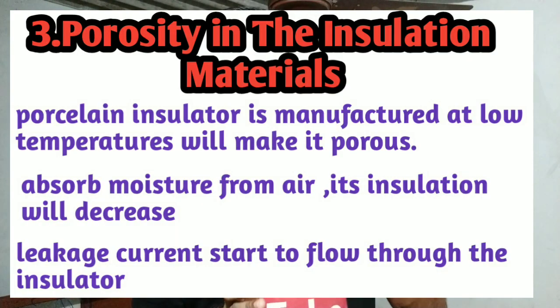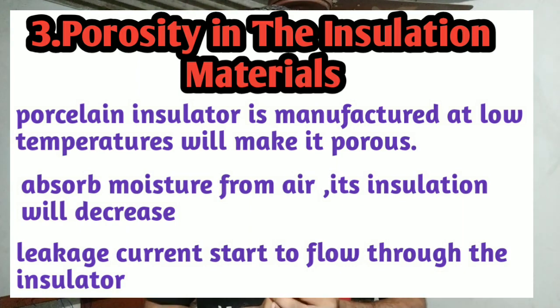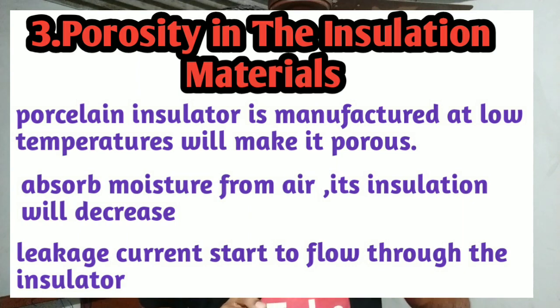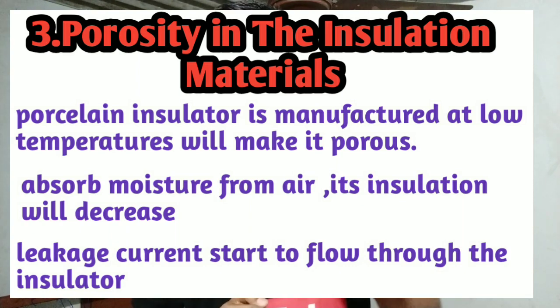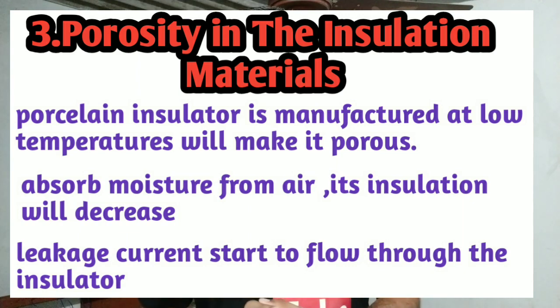If there are pores in the insulator, moisture will enter those pores. The pores will also accumulate dust particles. This reduces the high resistivity of the insulation. The moisture and dust cause the insulation resistance to drop, which leads to leakage current and ultimately damages the insulator.